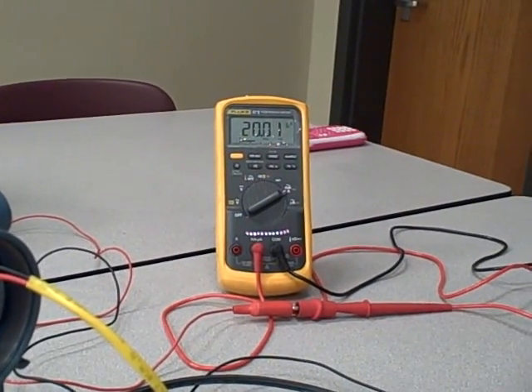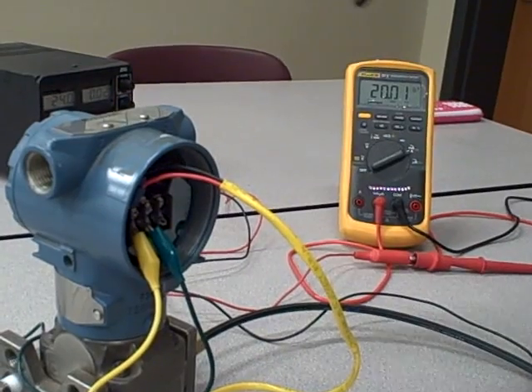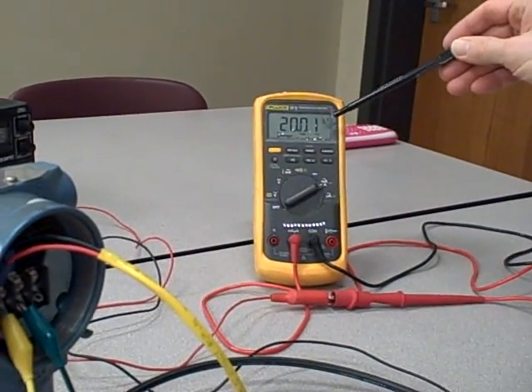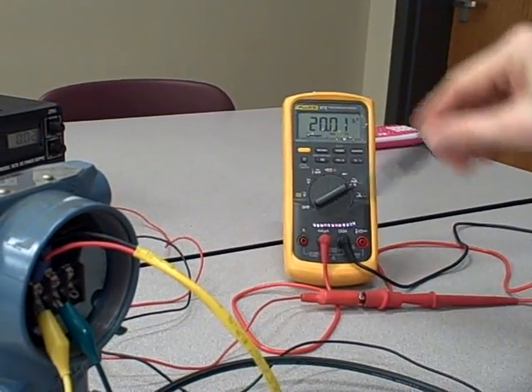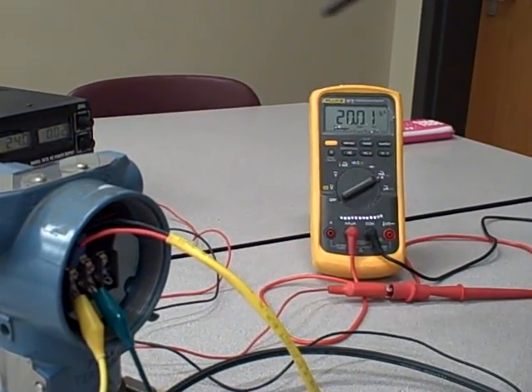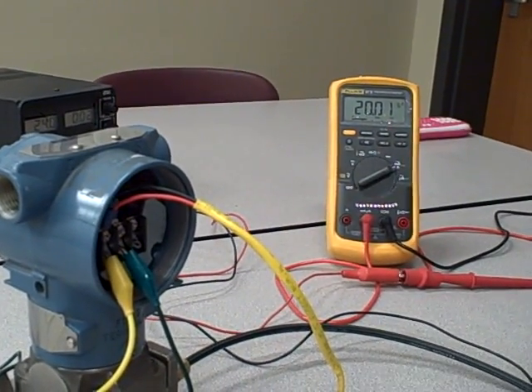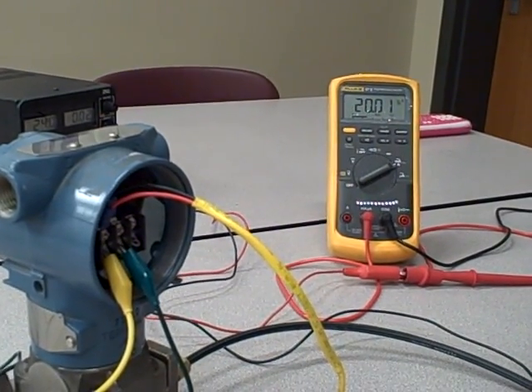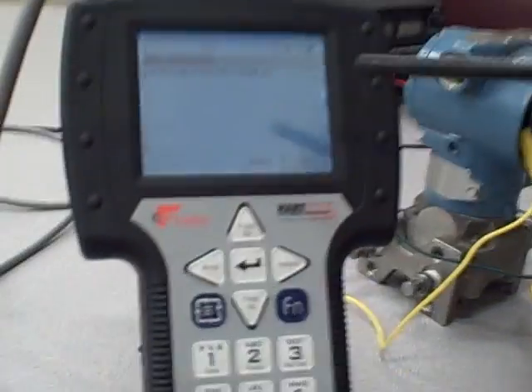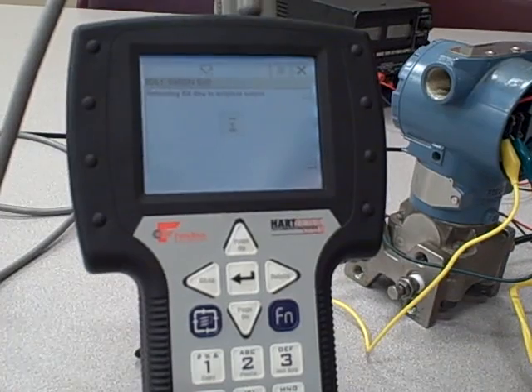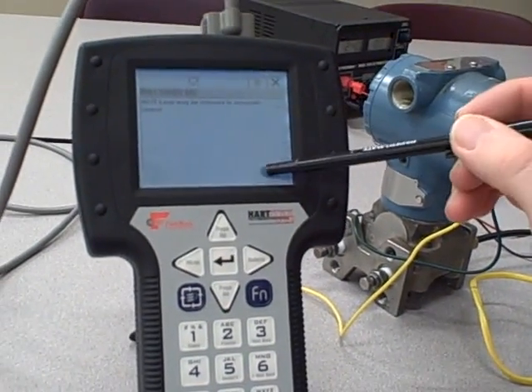As far as this transmitter knows, it is actually outputting 20.00 milliamps. If we see a discrepancy such as this, 20.01, it may mean that our testing instrument is out of calibration, or it may mean that the transmitter is actually outputting a little bit more current than it thinks it is, in which case we can fix that with what's called a digital trim. Let's go back and abort that test and explore some of the other menus.